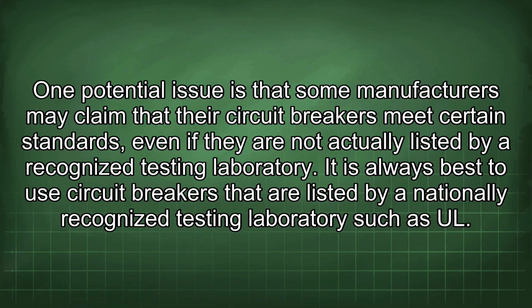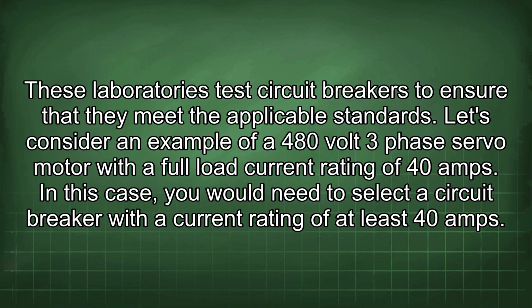One potential issue is that some manufacturers may claim that the circuit breakers meet certain standards, even if they are not actually listed by a recognized testing laboratory. It is always best to use circuit breakers that are listed by a nationally recognized testing laboratory such as UL. These laboratories test circuit breakers to ensure that they meet the applicable standards.